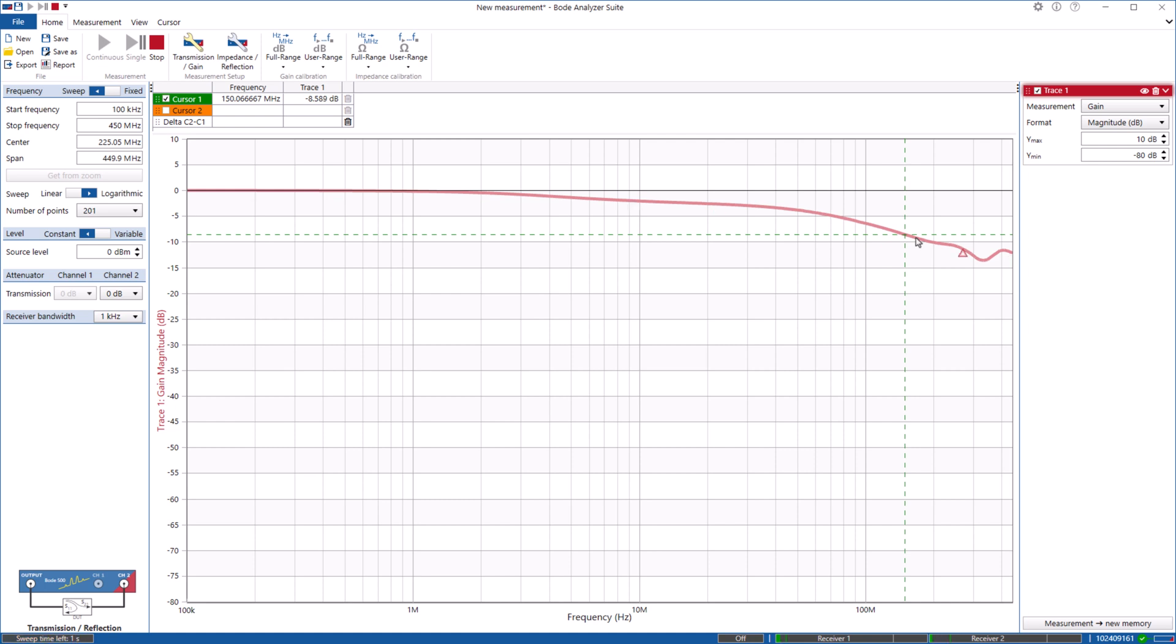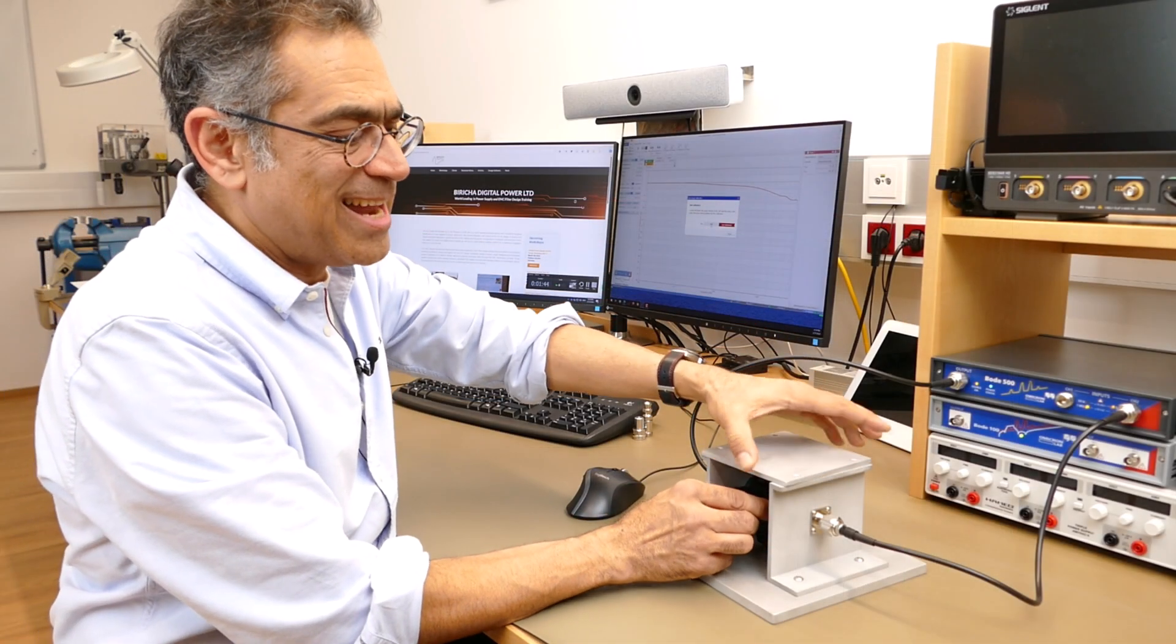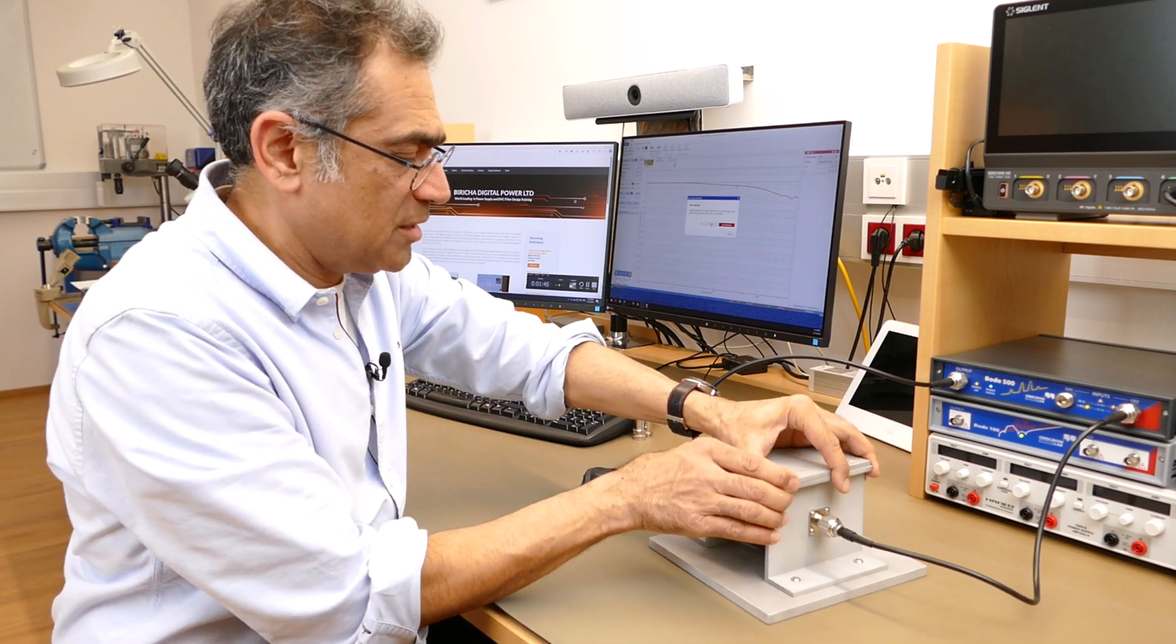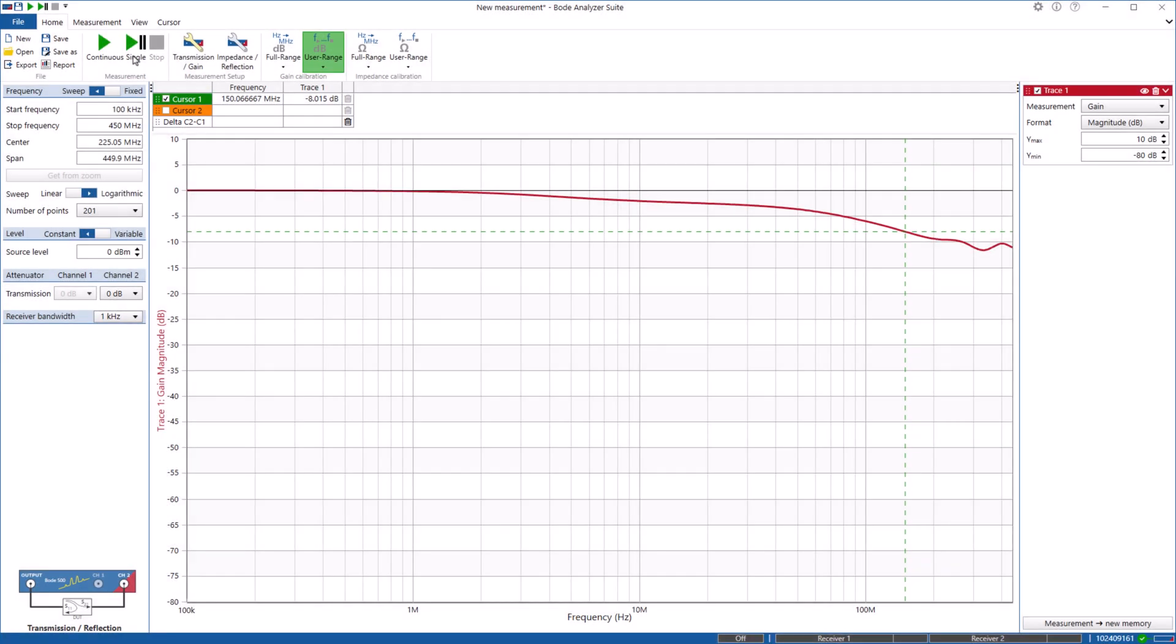So I go here and I go to user range and I will first do a calibration. Let me put this back on - in reality you should screw it back but for this measurement it's okay, we just leave it like so - and we do a calibration. And you will see that the instrument will take into account anomalies and make it a flat line.